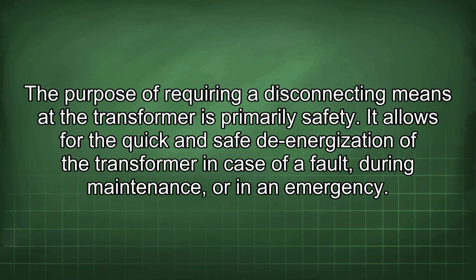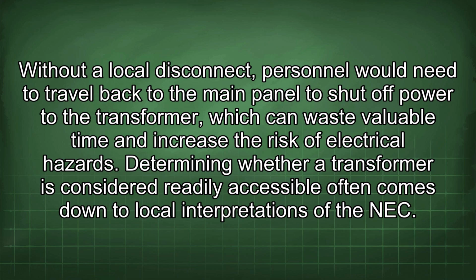The purpose of requiring a disconnecting means at the transformer is primarily safety. It allows for the quick and safe de-energization of the transformer in case of a fault, during maintenance, or in an emergency. Without a local disconnect, personnel would need to travel back to the main panel to shut off power to the transformer, which can waste valuable time and increase the risk of electrical hazards.